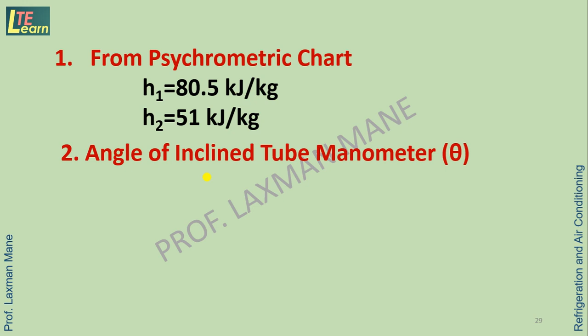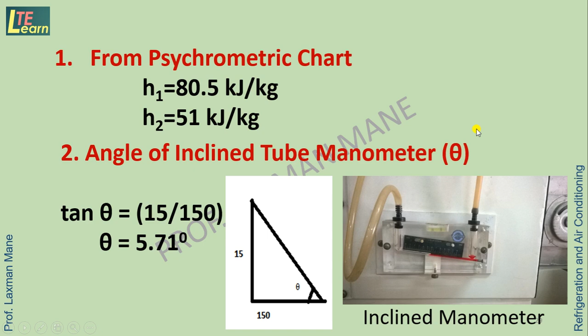Angle of inclined tube manometer. To find this angle, we need distances. So this is a triangle. 150 mm is the distance between these two vertical limbs, and these are the bottom points. 15 mm is the distance between these two points. So let us take the tan ratio, means tan theta is equal to 15 divided by 150. So angle theta is equal to 5.71 degree.